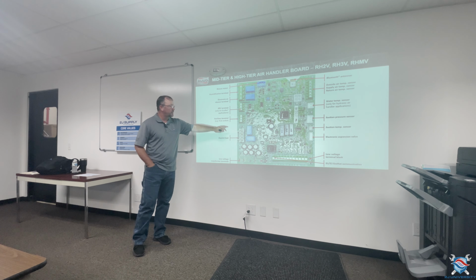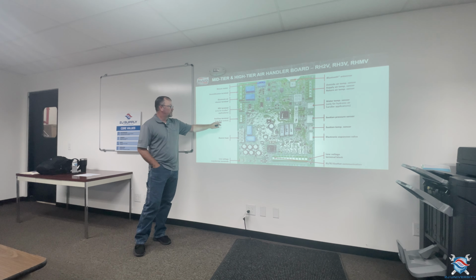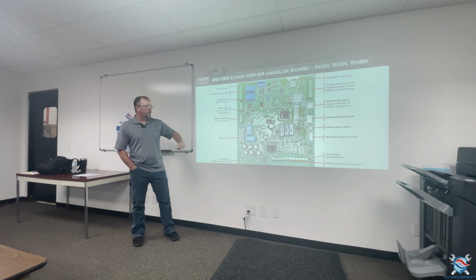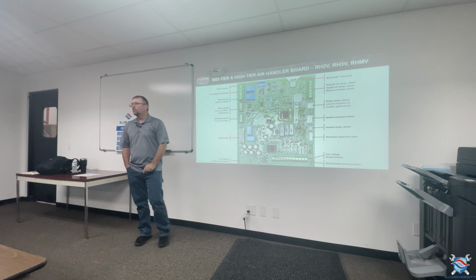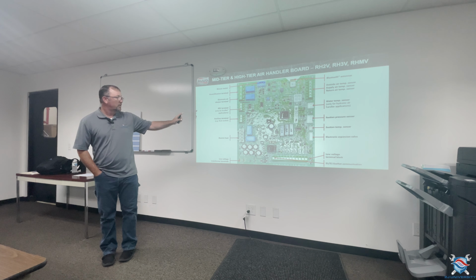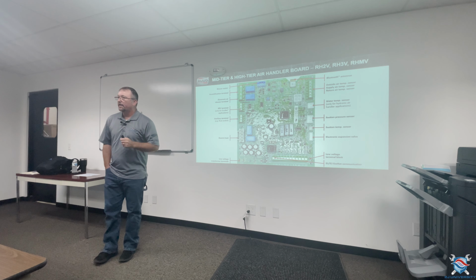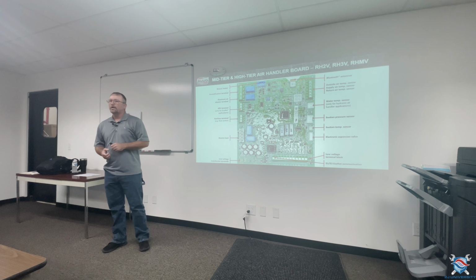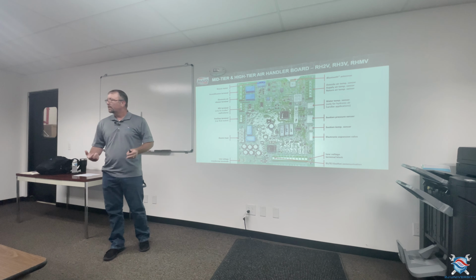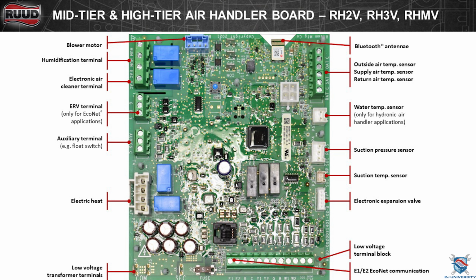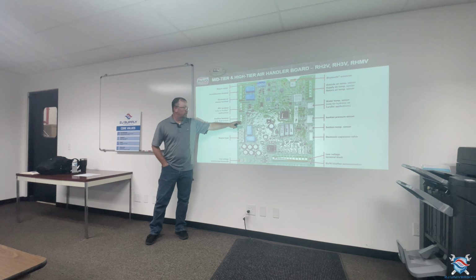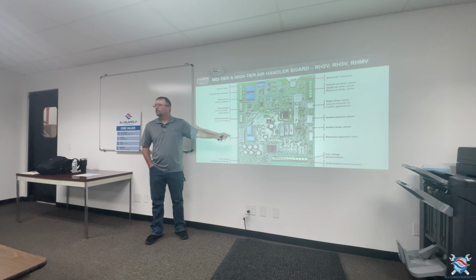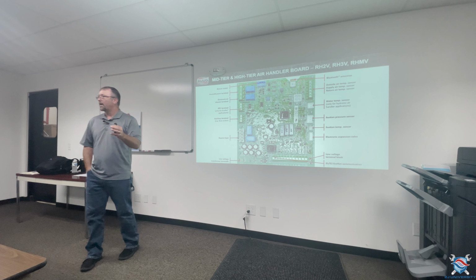Electric heat connection here, and then this float switch connection here. They've changed that on these new boards. You can hook a float switch up to that now, and if you're in an Econet compatible or even on the Contractor app, if that float switch opens, it'll alarm you that you have a float switch issue. So you're not going to run it in series, you're actually going to connect it to this CS&C now. Okay, and that's going to be your brake.